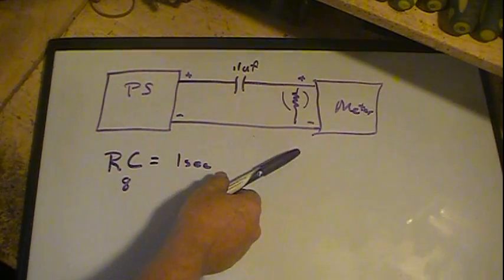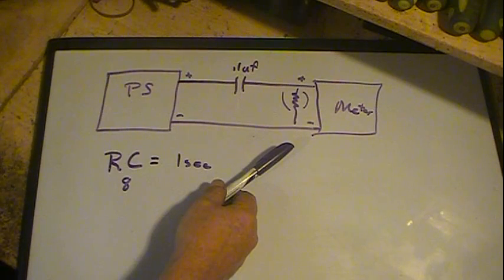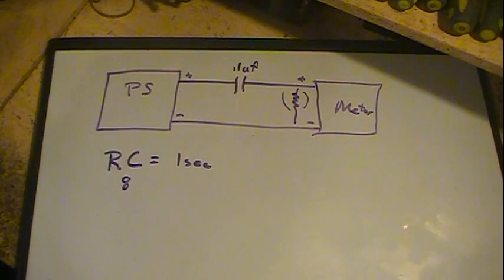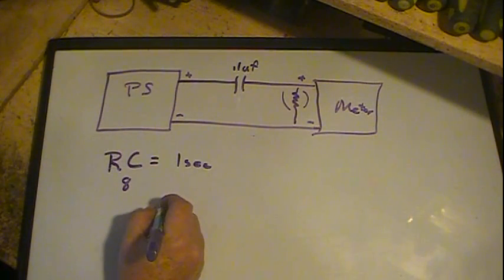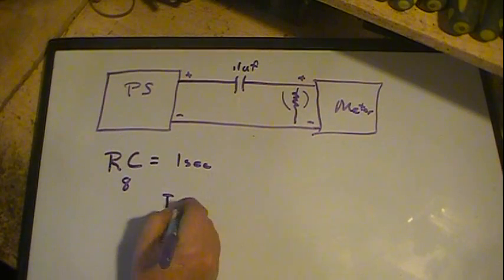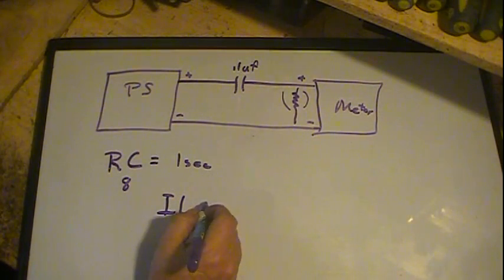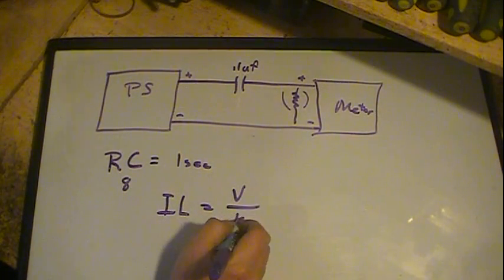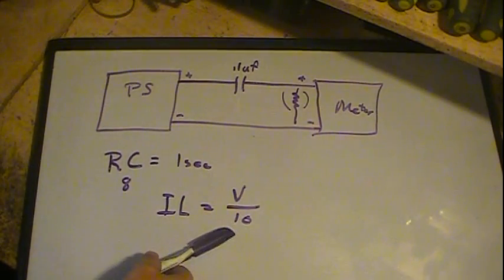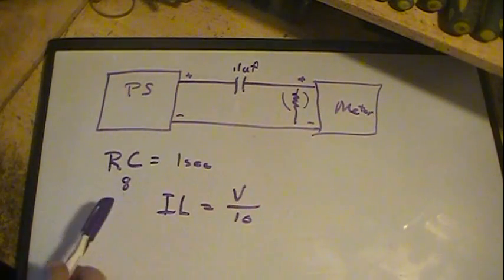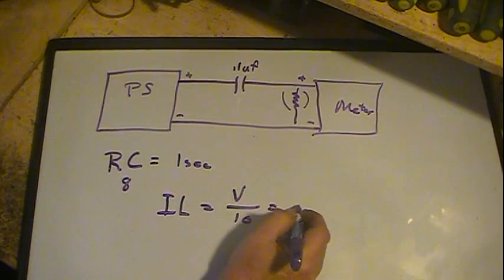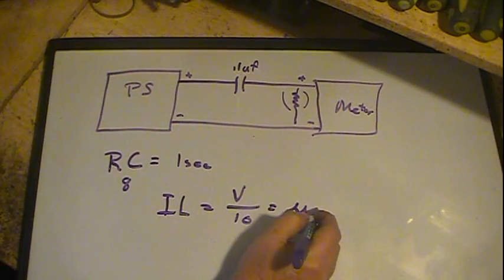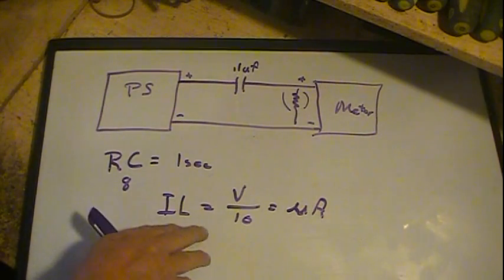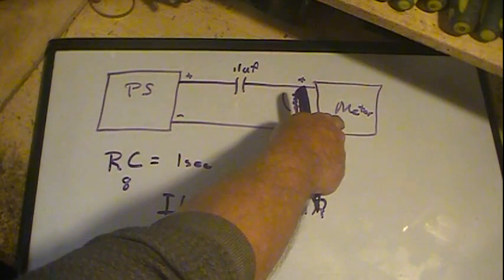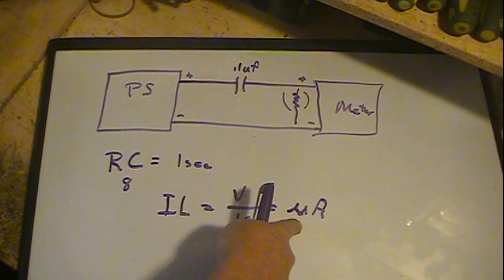So what you want to look at, there's a couple of formulas that you can use. First of all, what is leakage current and how do you find it? Well, we'll use IL for leakage current: IL equals V over 10. That gives us microamps, if my voltmeter reading is from a 10 megohm voltmeter. That's your leakage current formula. So just to find it, you take whatever reading you have on here and divide it by 10, and that'll turn it into microamps of current.